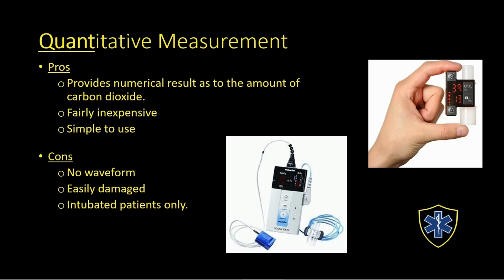We look at the one underneath it, that's attached into a pulse oximeter, where again, we have the blue probe there that goes on the patient's finger to measure the oxygen saturation level, and on the blue wire to the right of the machine, we have a little spacer that goes in between the bag and the ET tube, and the readout will give us, again, the numerical series like we have on the one up top. Now those there are a little bit more durable than the one up on top, but again, there's no waveform, and they only really work on intubated patients. We've got to sort of have a tube there to connect the tube connection to.